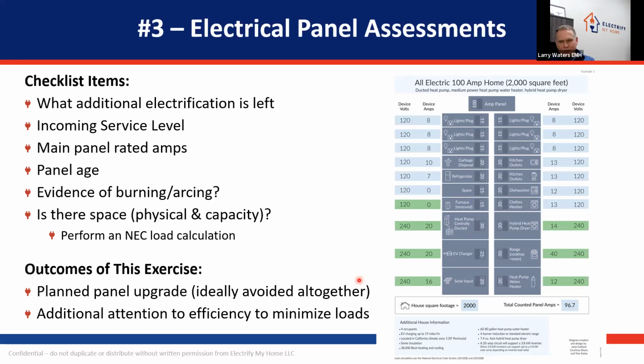We know that the utility companies are not necessarily being friendly with us about upgrading panels as easily as we used to. Figure out the main panel rated amps, look at the panel age, look for evidence of burning and arcing, and is there physical space and capacity space within the system? And we know in order to determine capacity, we're not looking at all the breakers full. We're looking at the actual National Electric Code load calculations to find out if there's more space available on that panel. Just because it's full of breakers does not mean it's at capacity.